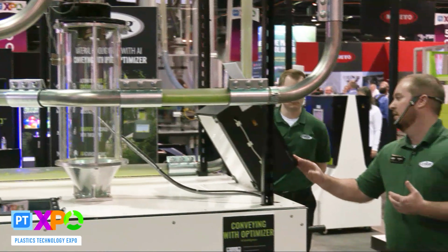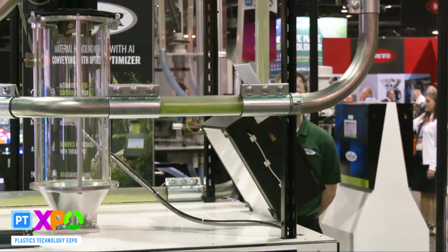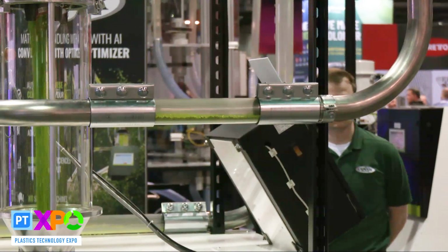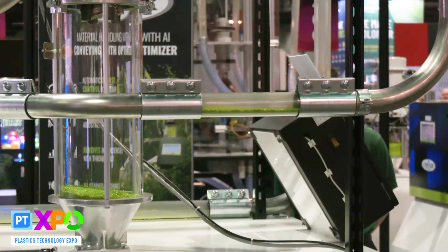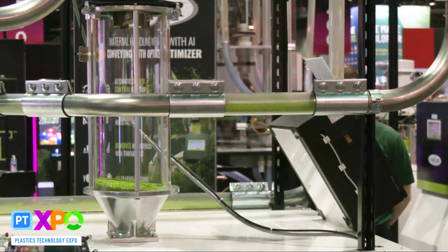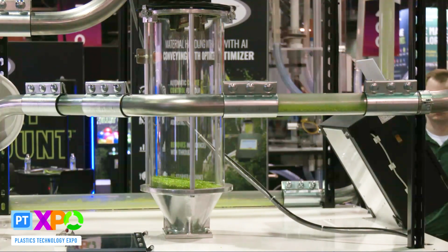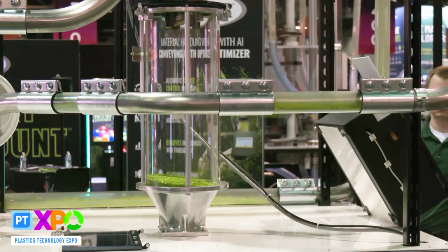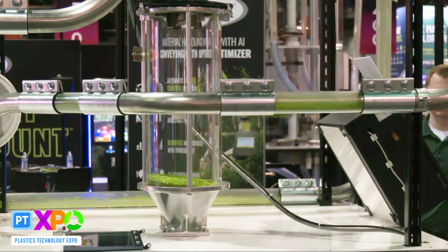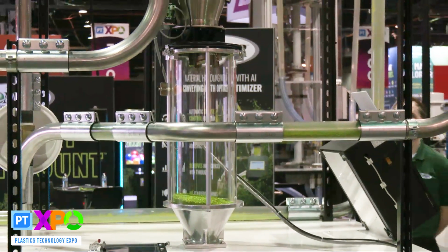So we're trying to run right around 8.5 inches of mercury on our vacuum pump. Once we induce this leak, we're only running about 6 inches right now. So we're detecting that change from 8.5 down to 6. And now our valve is going to start modulating. It's going to start changing to boost that vacuum pressure back up and ultimately get more material back in the line so that I can get material to our machine the way we need it to.